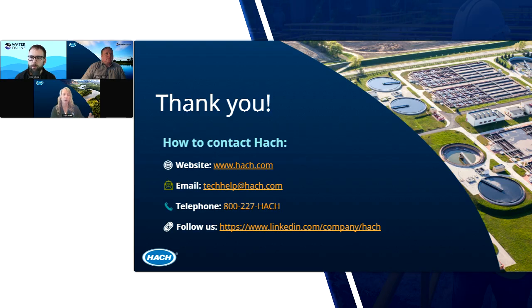Now, once they went with the online unit, what could they do then? You're right, you don't necessarily know what's coming at you and when, but if you're trending that information, you have more reaction time. So once they went with the online analyzer, he's still manually controlling his chem feed pump, but it's off of real-time numbers and not just a 24-hour composite where you're left wondering when did I get that spike.